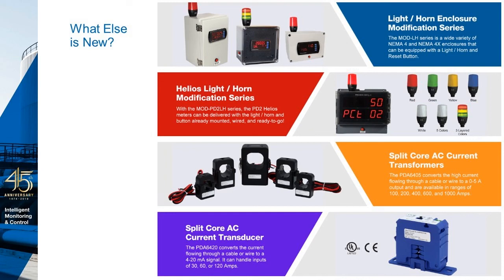A few other products we've recently made available for sale, and you'll likely see some webinars on soon, are our split core AC current transformers. These let you measure up to 1,000 amps without having to make any disconnects, since it's a split core device, and then output that as a 0 to 5 amp signal into products like our PD6400 meter.